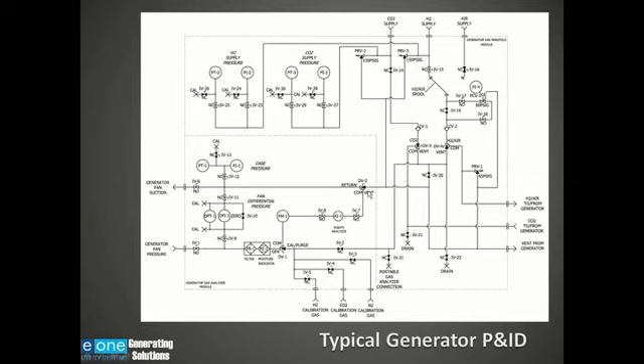We have to change this valve to go to vent instead of return to the generator. So now I'm relying on the generator case pressure to push a sample through the analyzer out to vent, and I'm using a small amount of hydrogen to monitor my hydrogen purity. Here we have the calibration ports for the gas analyzer, and these can either be tied in permanently to gas connections, or they could be bottles brought in temporarily to calibrate the piece of equipment.